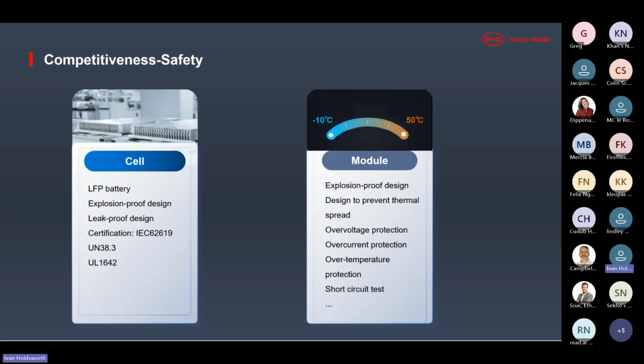Regarding the modules, very, very safe in terms of cell safety. LFP is an inherently safe cell chemistry, and your operating temperatures are between -10 and +50. There is a bit of derating in cold weather, and your charging derates more than your discharge. There are also a lot of protections in the PDU. The PDU will disconnect if there's any issues such as overvoltage, overcurrent, overtemperature, or any short circuits. So the PDU will protect that tower from any external interference.